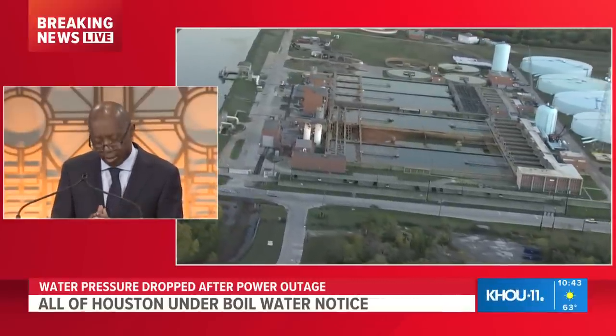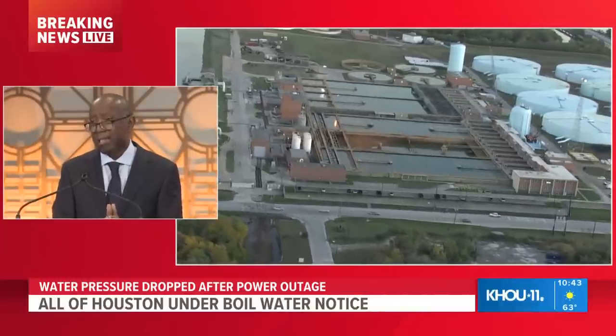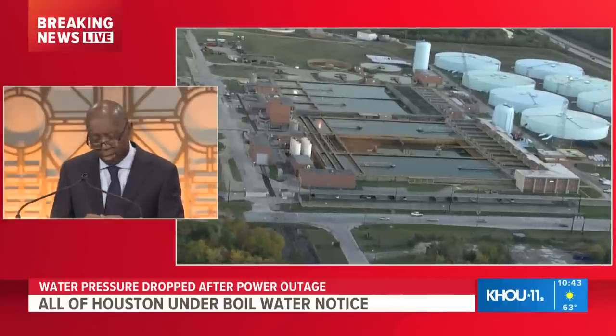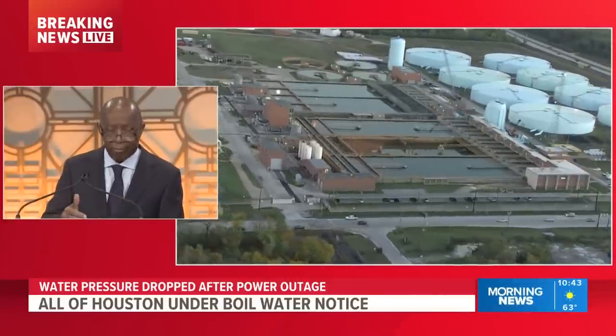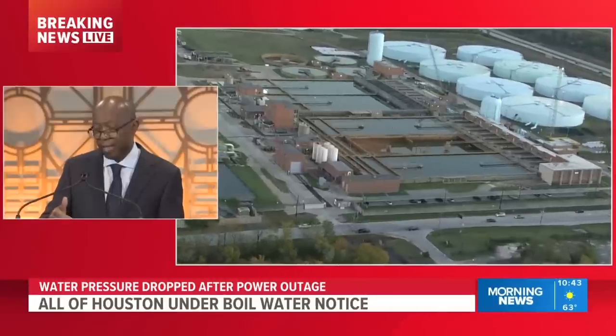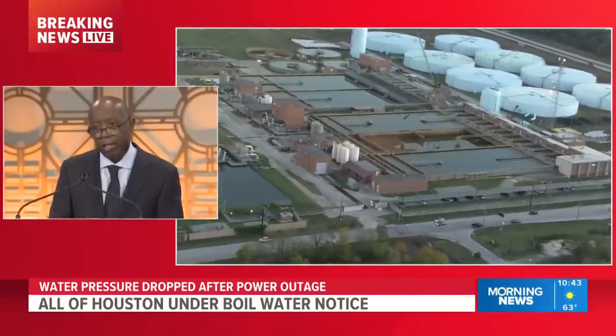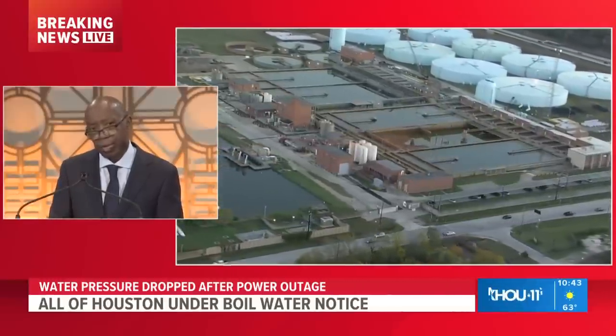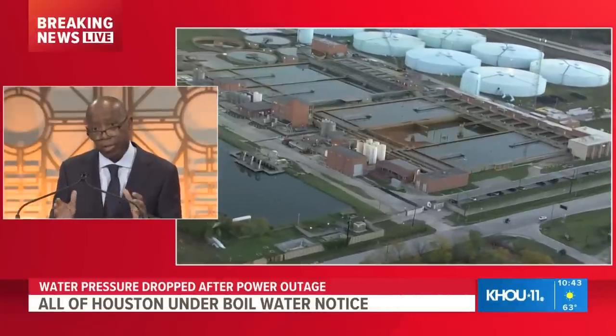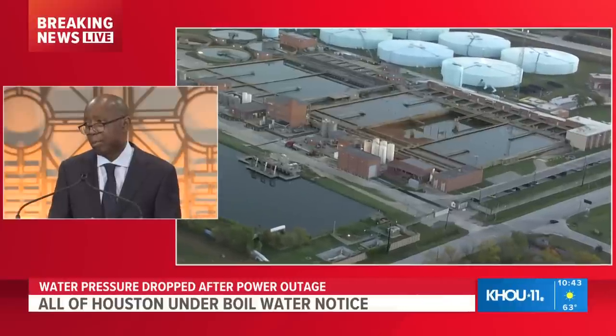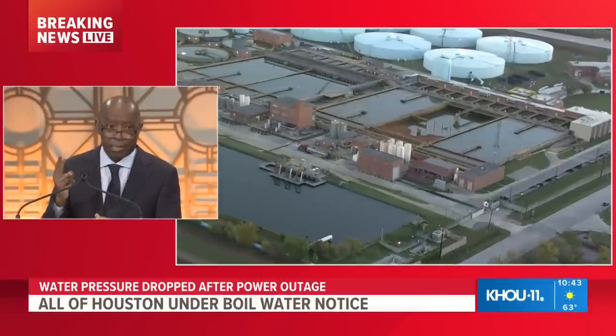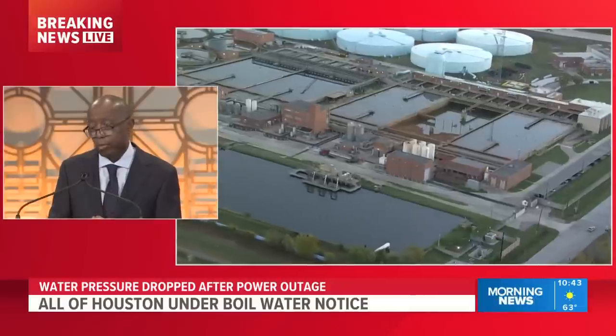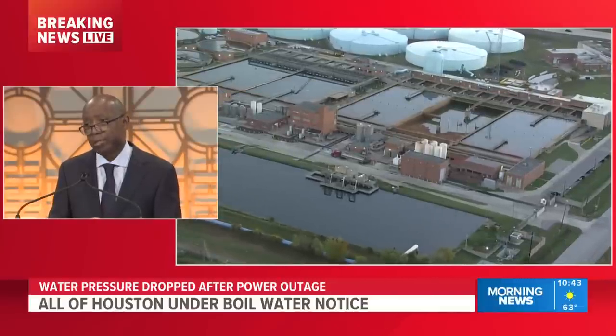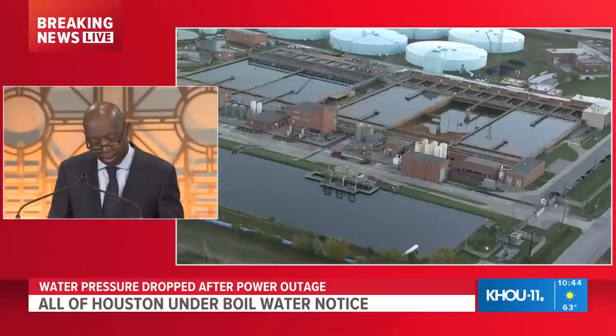Conversations with TCEQ were taking place from 2:43 p.m. up to 6:40 p.m. Based on the data from the sensors, a decision was made that a boil water notice was to be issued. One reason it took that long is that for 14 of the sensors, pressure remained below 20 psi for less than 2 minutes, and for two sensors it remained below for about 30 minutes. So there were questions as to whether a boil water notice even needed to be issued. A decision was made out of an abundance of caution to issue the notice, and it was done.